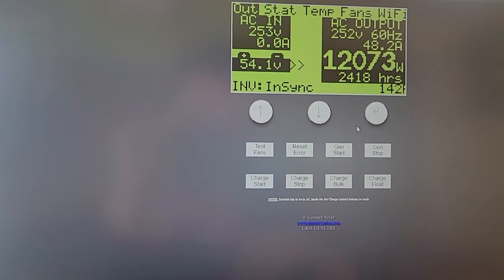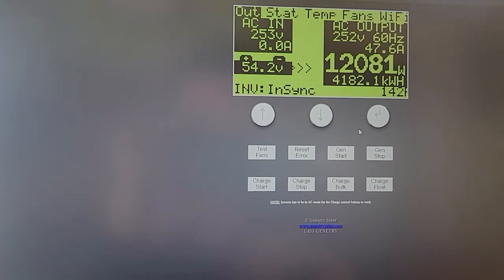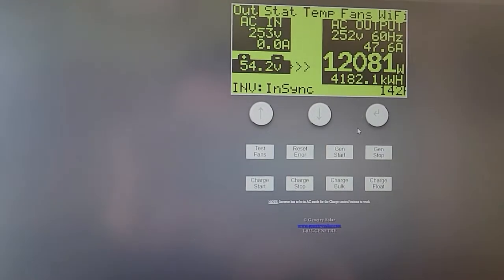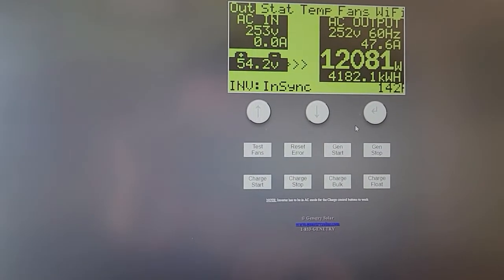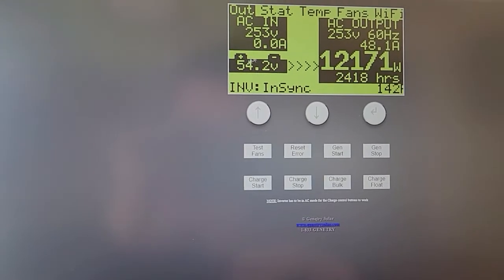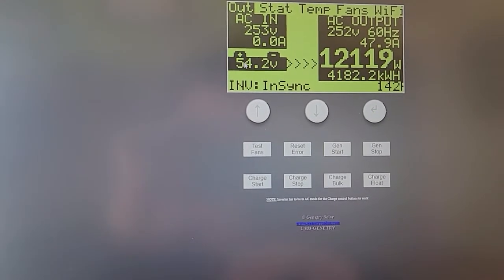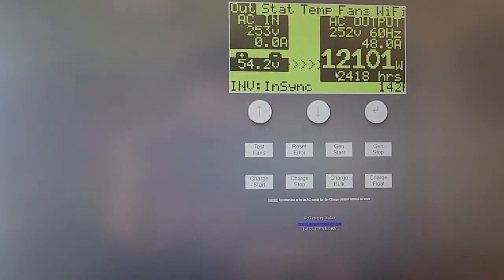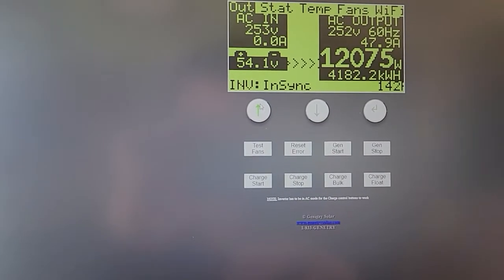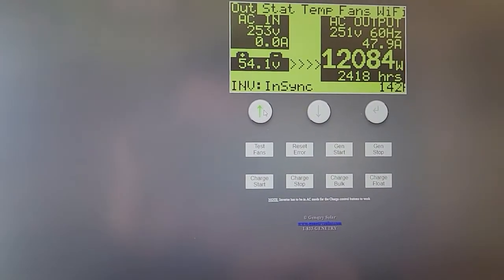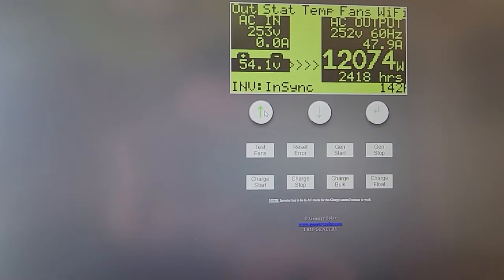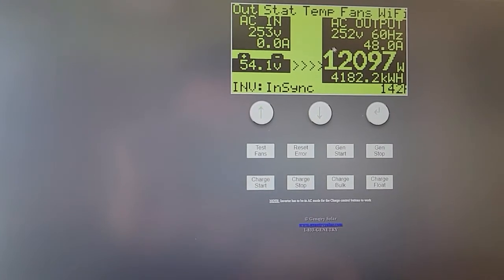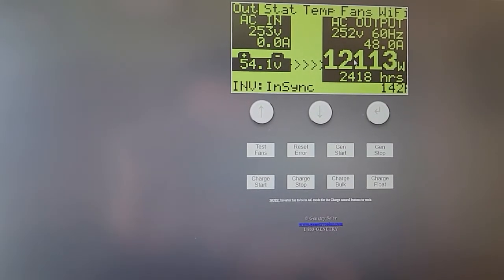So, very interesting. Well, you're holding at 12 kilowatts. I will, of course, update it, and I am going to do a 13 kilowatt load test as well. That'll have to be after these batteries charge back up. But, I'm going to let this run all the way down to about 52 volts, just making sure everything's fine. I'll probably do an update video after that, and then, I'm going to go for a 13 kilowatt load test thereafter.